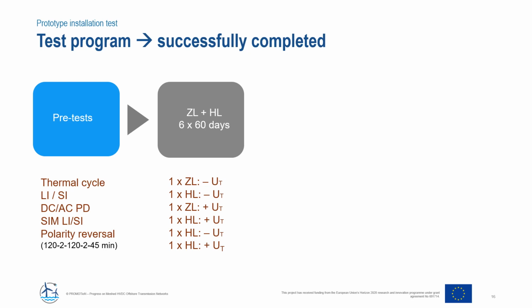And there are different load conditions. There is a zero load and a high load. Zero load means the DC GIS is put under a DC voltage, but there is no current running in the bus duct. The high load means the DC GIS is subjected to the DC voltage plus a current of 4000 amps running through the bus duct.